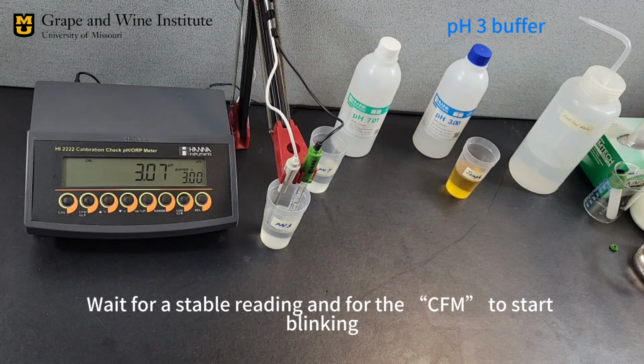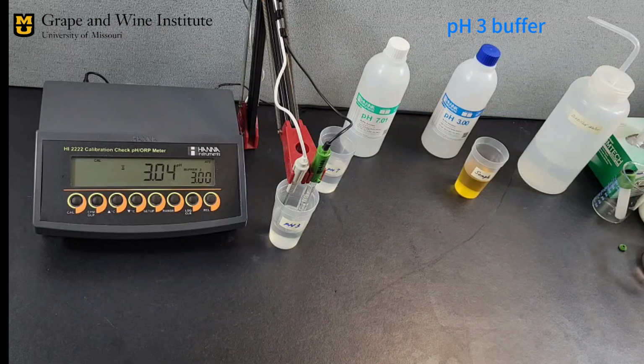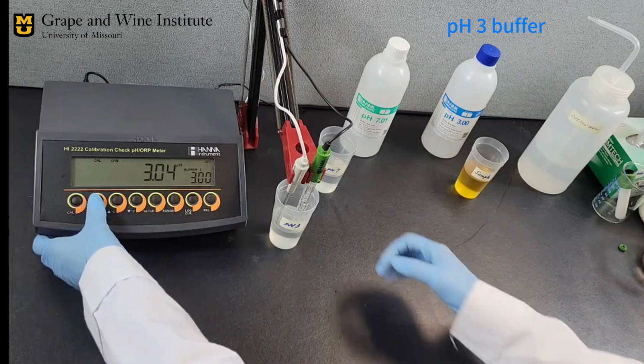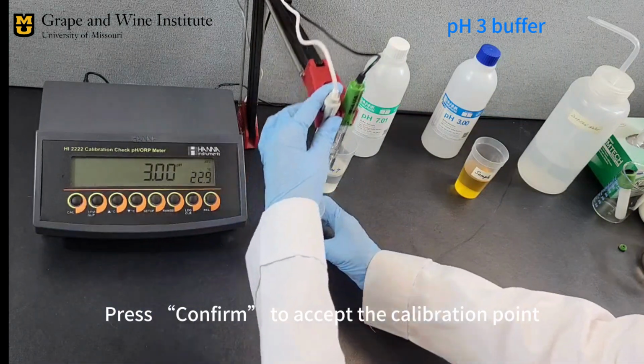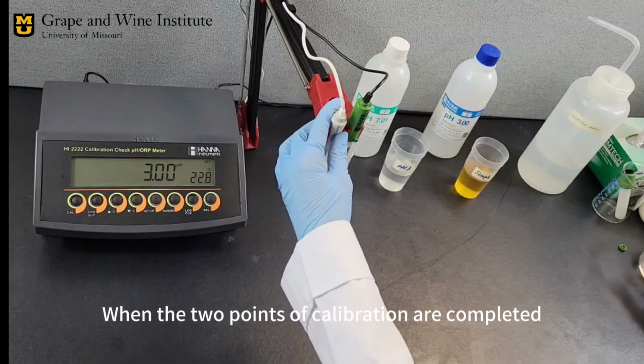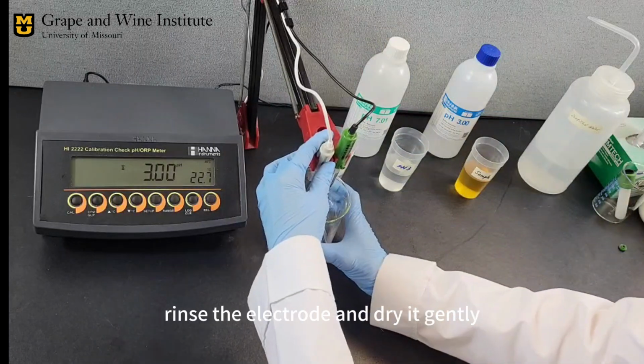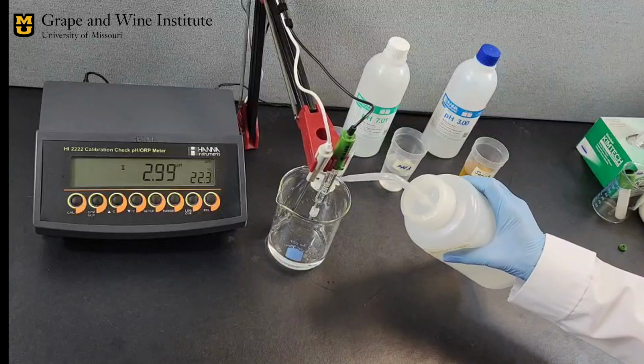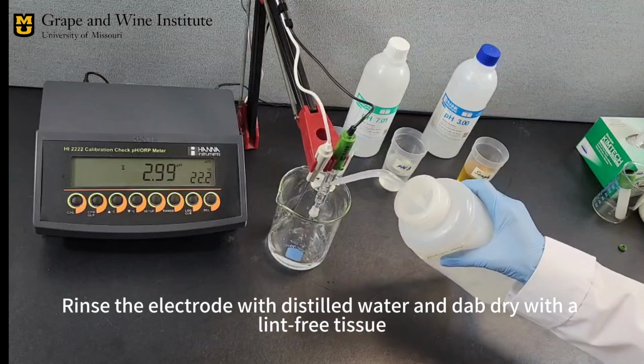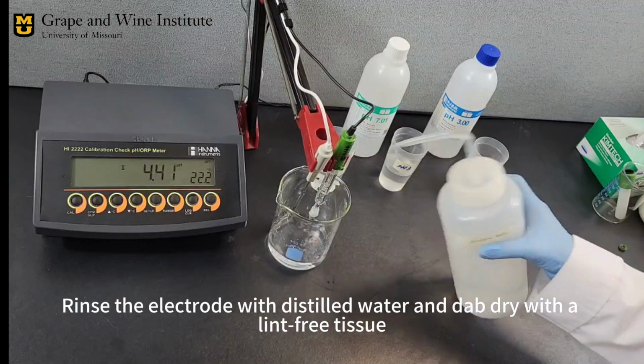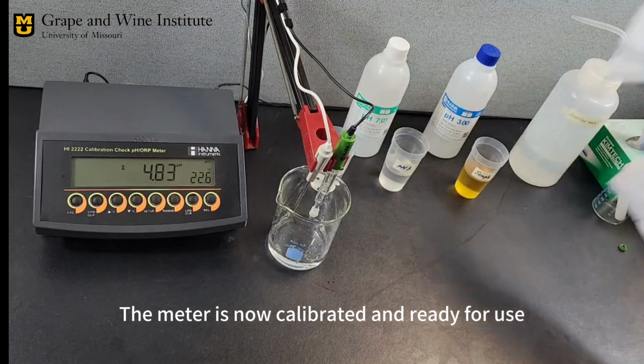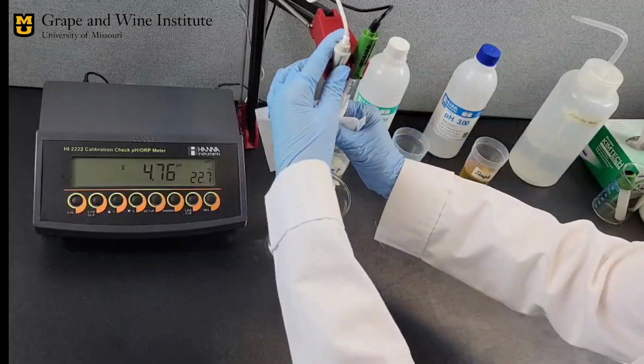Wait for a stable reading and for the CFM to start blinking. Press confirm to accept the calibration point. When the 2 points of calibration are completed, rinse the electrode and dry it gently. Rinse the electrode with distilled water and dab dry with a lint-free tissue. The meter is now calibrated and ready for use.